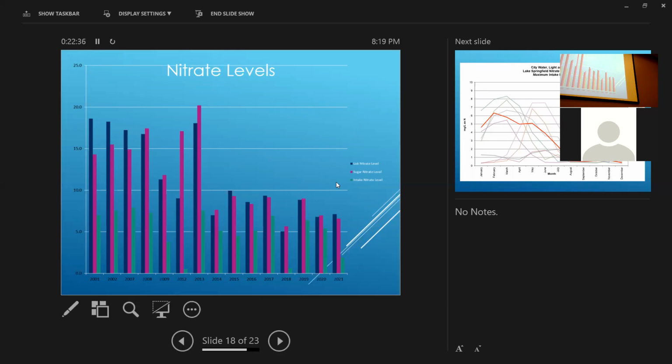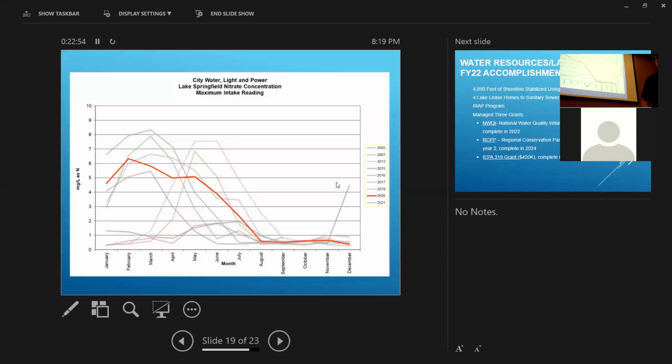So God willing, once we get those high levels out west and out south, we've got enough residence time in the lake that those numbers will come down below the drinking water standard of 10 parts per million. One of the big issues with this is that it's an acute type violation.